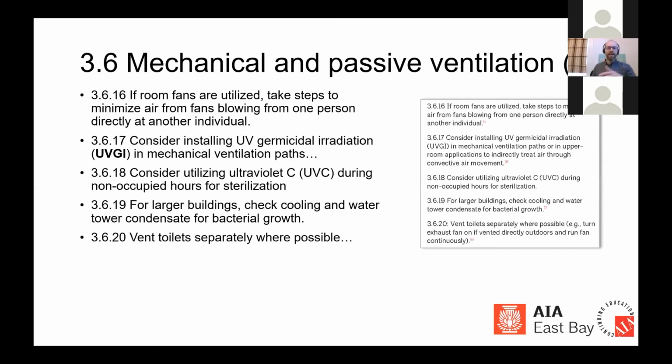And so besides these kind of standalone machines as a janitorial type supplement, they can be installed into ductwork, and it's a really interesting solution that you may consider for your buildings. Now there is this bullet point here I just want to point out: there are different kinds of ultraviolet light, ultraviolet A, B, and C, and consider using ultraviolet C during non-occupied hours for sterilization.